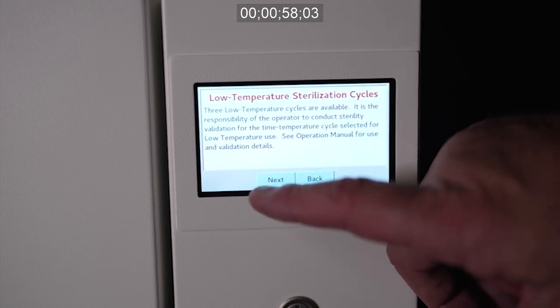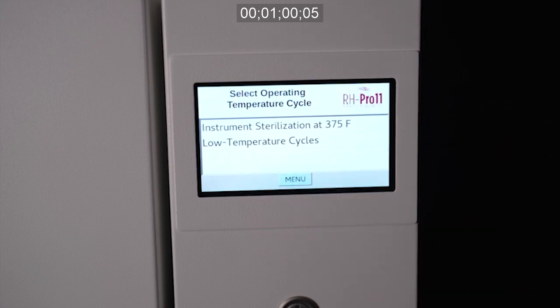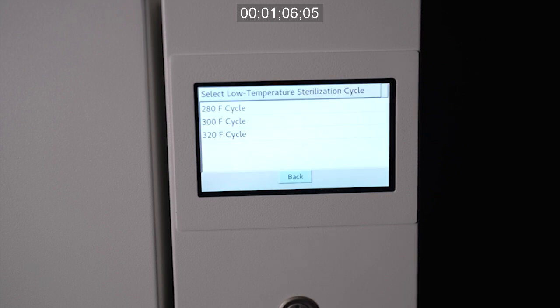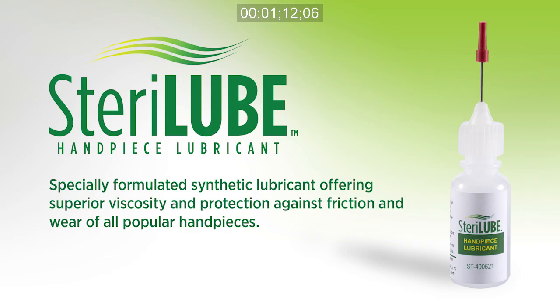Select and press the temperature cycle that you will be using to sterilize instruments, either the 375 Fahrenheit cycle for faster turnaround and high heat-resistant instruments, or any one of the 3 low-temperature cycles for instruments incompatible at the 375 temperature cycle. Note that when sterilizing handpieces at the 375 temperature, synthetic lubricants must be used during routine handpiece maintenance.